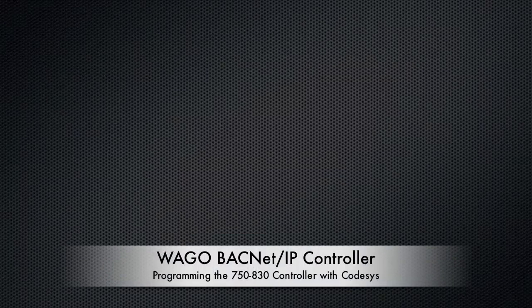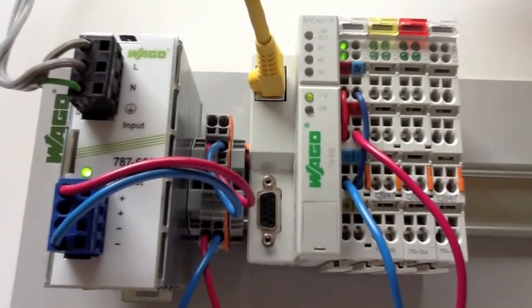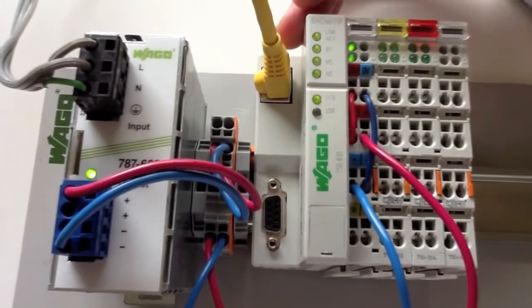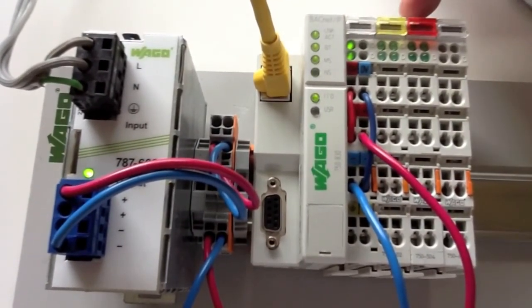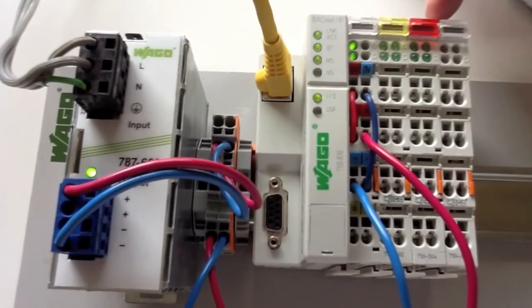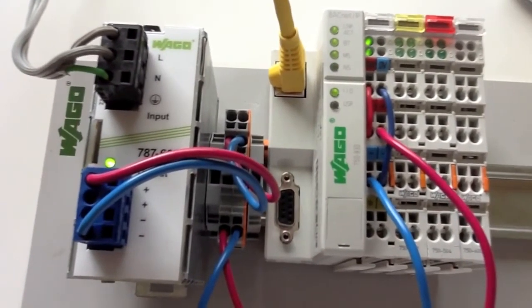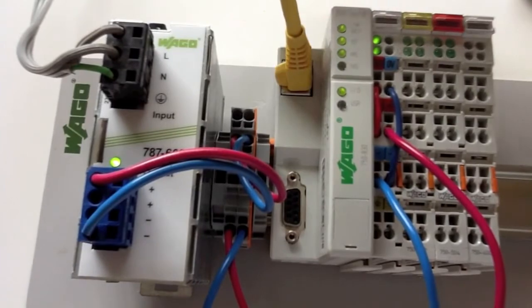Going to program the WAGO BACnet IP controller. What we have here is a 750-830 connected to a 4-channel digital in and a 4-channel digital out. This controller is also a Modbus TCP master, so it makes a really good gateway. I'm just connecting this to my network here with the Ethernet cable.